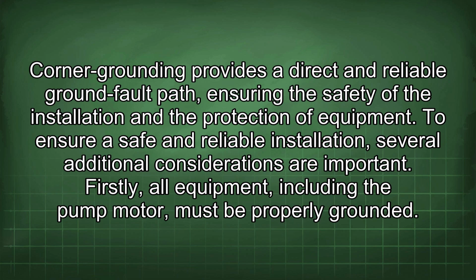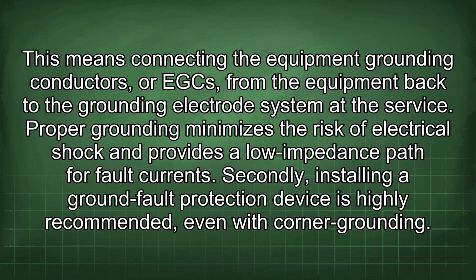Firstly, all equipment, including the pump motor, must be properly grounded. This means connecting the equipment grounding conductors, or EGCs, from the equipment back to the grounding electrode system at the service. Proper grounding minimizes the risk of electrical shock and provides a low impedance path for fault currents.